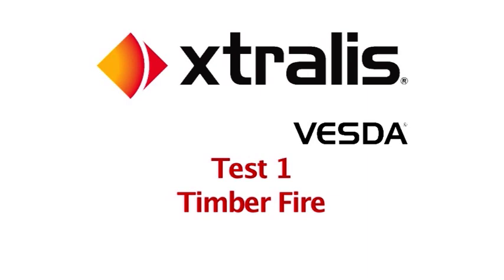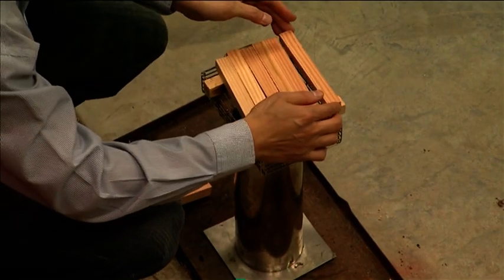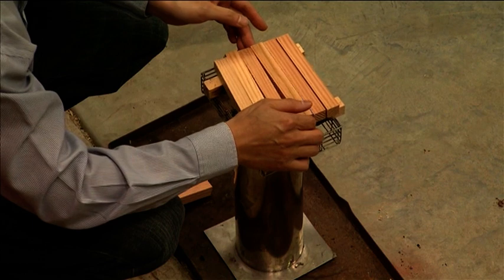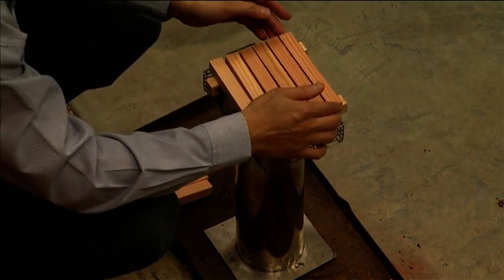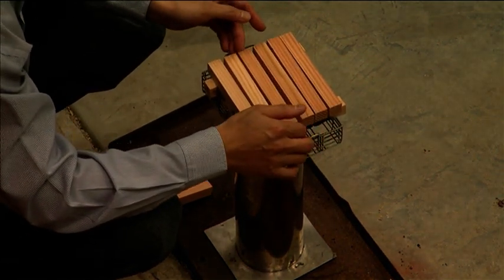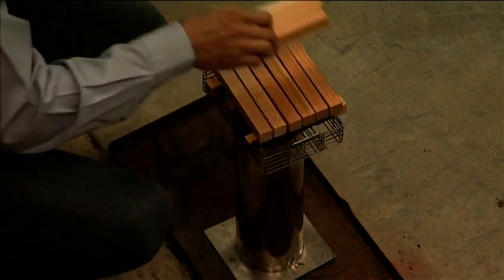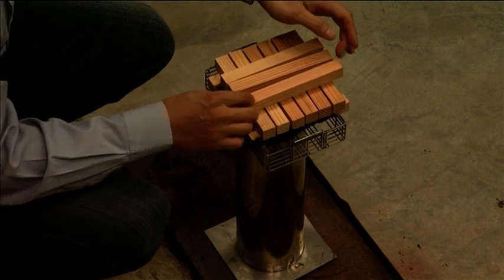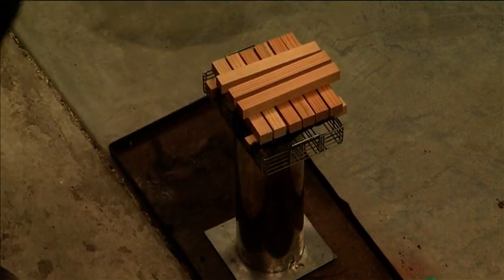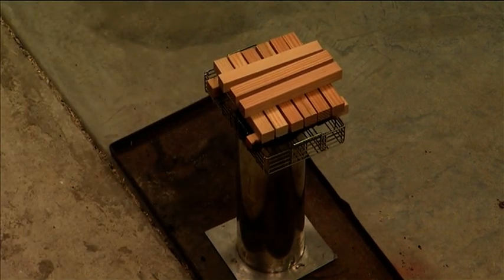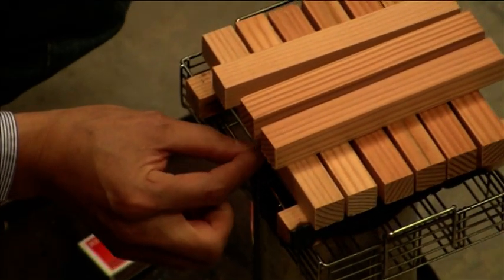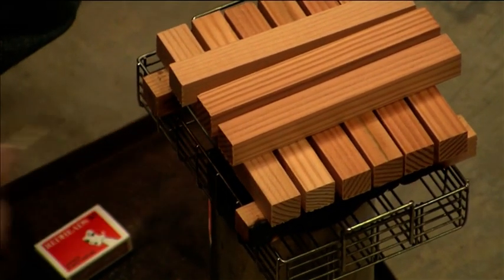Timber fire. The first test is conducted to UL standards and is a small timber fire, which produces a fire between one to two kilowatts. The test will be carried out firstly with the warehouse doors closed and then open to simulate the effect that air flow will have on smoke and the time taken to detect smoke for the three technologies.